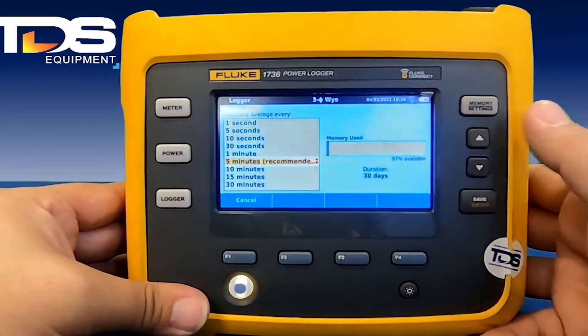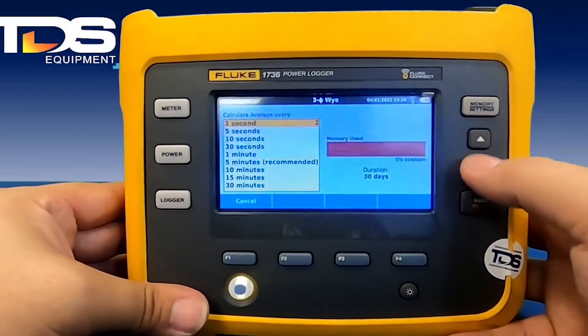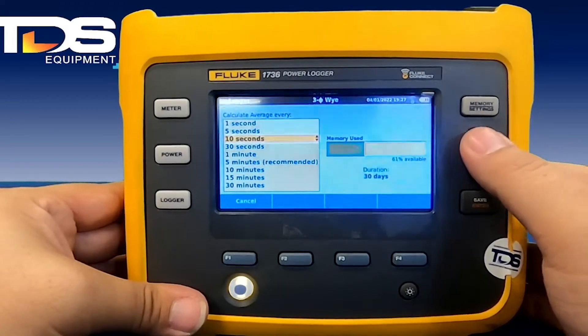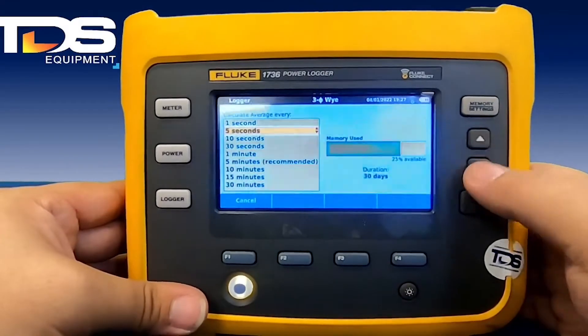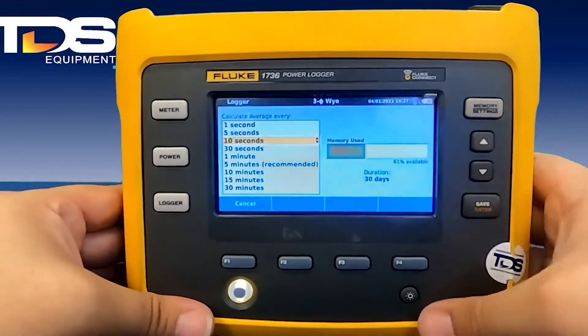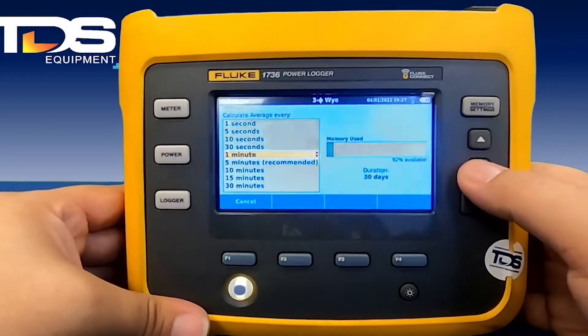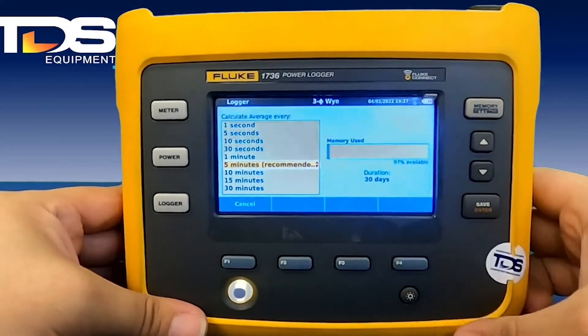The average setting lets you tell it how often you want it to take average readings — from one second up to 30 minutes. On the right side you can see your memory usage. The faster average you select, the more memory it uses up. For example, at 10 seconds it uses up about half the memory, which makes the file large and hard to work with in the software. Personally, I like to stick with the recommended 5-minute average — after a 30-day recording you'll still have 97% of memory available.